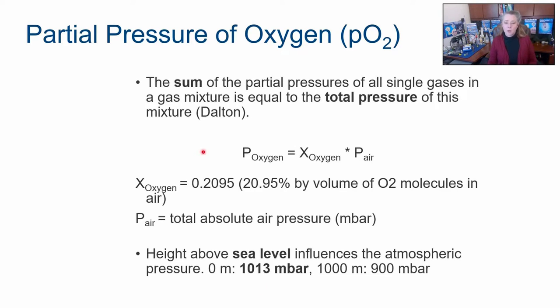When we're thinking about oxygen, the partial pressure is equal to the concentration of oxygen times the pressure of the air. So if we think about X equals 20.95% by volume oxygen in the air, the partial pressure of dissolved oxygen is that times the partial pressure of air, or the total pressure. Atmospheric pressure has a significant impact on this.